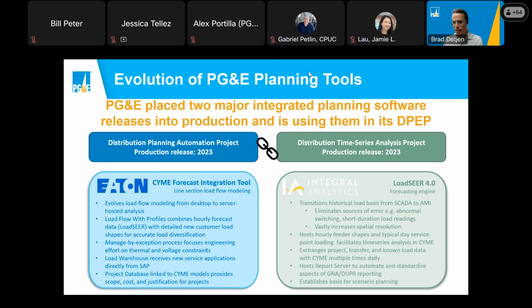CYME pulls that data back in and undertakes the primary voltage load flow modeling. LoadSeer also hosts hourly feeder shapes, and these two new platforms work together to improve our ability to model load diversity by combining incoming load hourly shapes with feeder and bank historically informed base shapes and forecasts, so that we are not making worst case scenario assumptions about the load that a new customer will come online with, but instead overlaying the new customer load shape with the feeder shape as well.